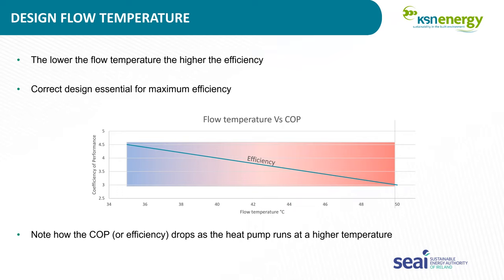So it's drastically different. Typically, gas is normally a third of the price of electricity. So heat pumps run at a high temperature may have no cost savings to the end user. So design is really important. If we can design a heat pump to run at low temperatures, that's where we'll get the heat pump working optimally.